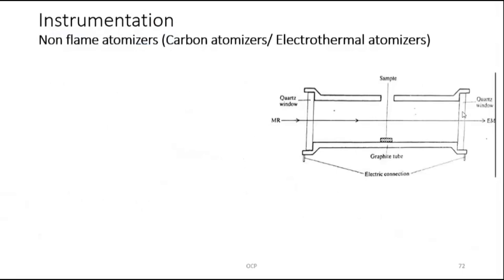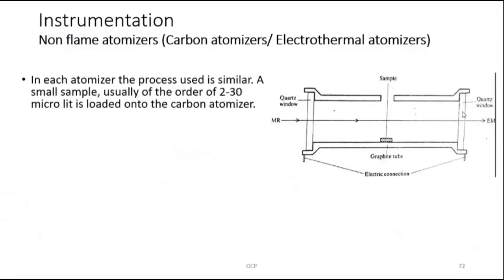Let's start with the carbon atomizer / electrothermal atomizer. In each atomizer the process is similar. We basically heat carbon in rod format. A small sample — typically 2 to 30 microliters — is loaded onto the carbon atomizer; the sample is injected or placed on a graphite tube through an opening.